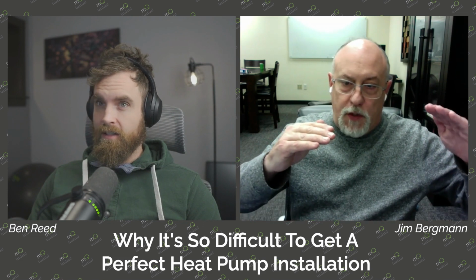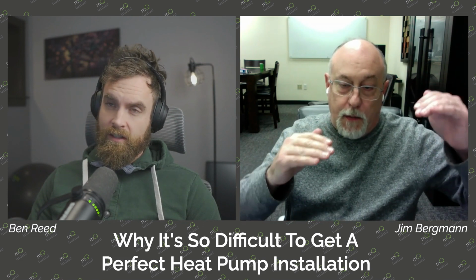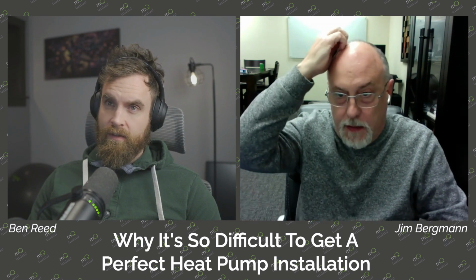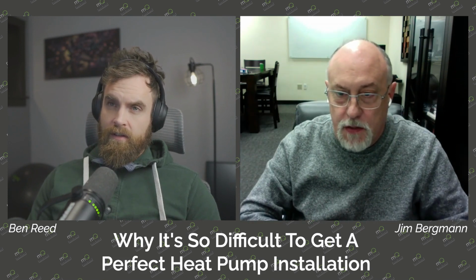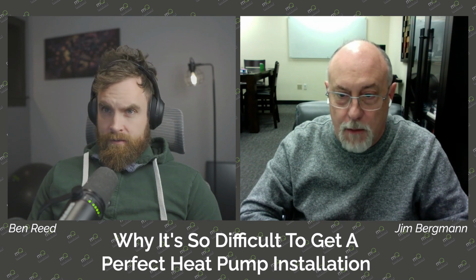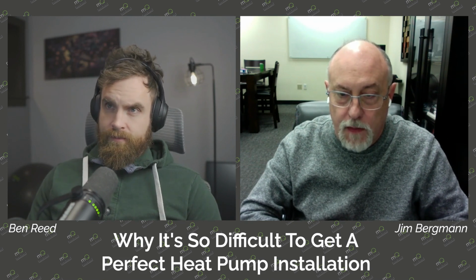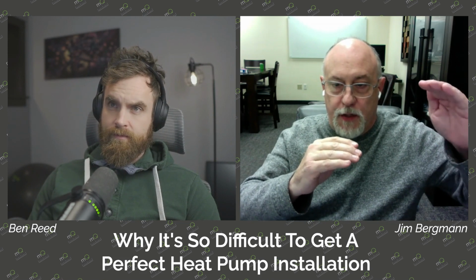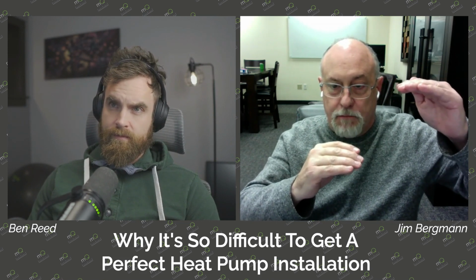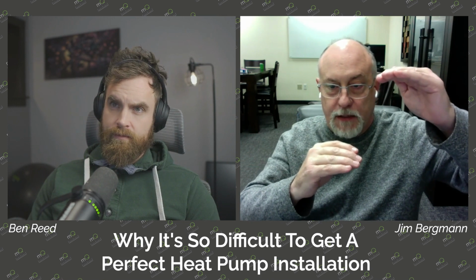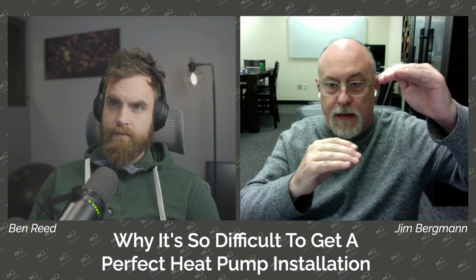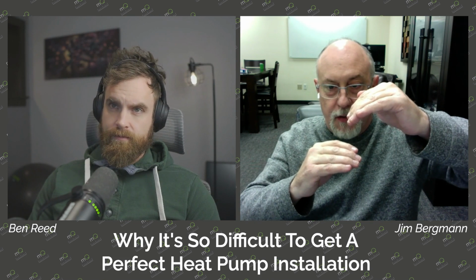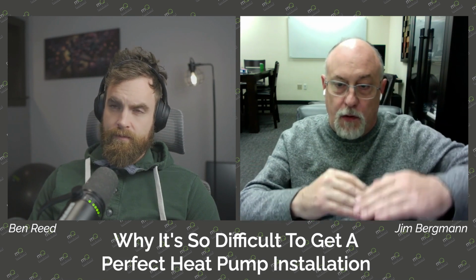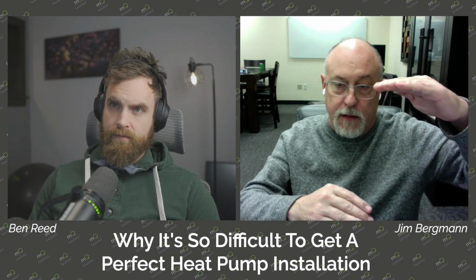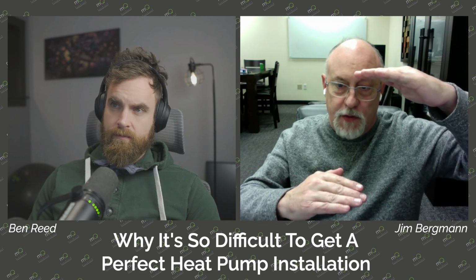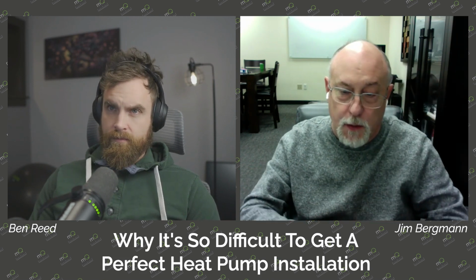So, some of what we're trying to watch for is what I watch for when I add refrigerant on a heat pump: is my BTUs going up, right? Is my output going up? Is my EER going up? Because if I add a little refrigerant in and I see an increase in capacity, then I'm going the right direction. Add a little more gas and increase capacity. Eventually it's going to plateau. If we keep adding more refrigerant, it's going to go down in capacity because now I've crossed that point of maximizing that indoor coil space, and now I'm stacking it in there, basically making it into a liquid line.